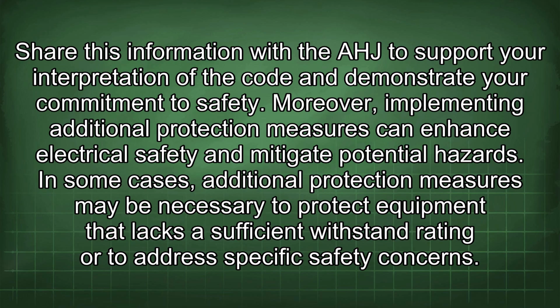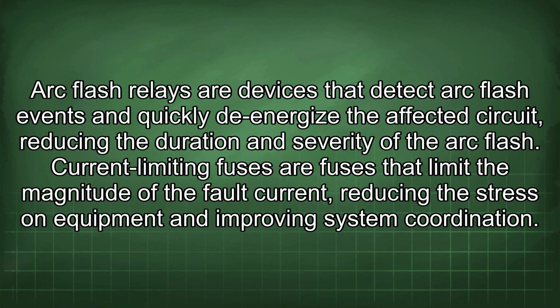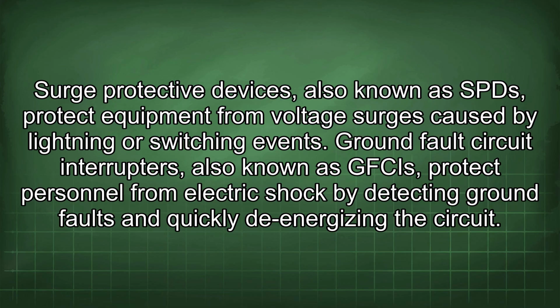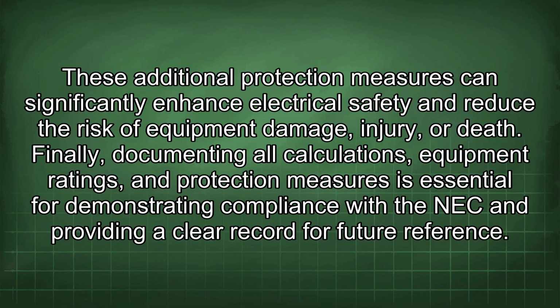Moreover, implementing additional protection measures can enhance electrical safety and mitigate potential hazards. In some cases, additional protection measures may be necessary to protect equipment that lacks a sufficient withstand rating or to address specific safety concerns. Arc flash relays are devices that detect arc flash events and quickly de-energize the affected circuit, reducing the duration and severity of the arc flash. Current limiting fuses are fuses that limit the magnitude of the fault current, reducing the stress on equipment and improving system coordination. Surge protective devices, also known as SPDs, protect equipment from voltage surges caused by lightning or switching events. Ground fault circuit interrupters, also known as GFCIs, protect personnel from electric shock by detecting ground faults and quickly de-energizing the circuit. These additional protection measures can significantly enhance electrical safety and reduce the risk of equipment damage, injury, or death.